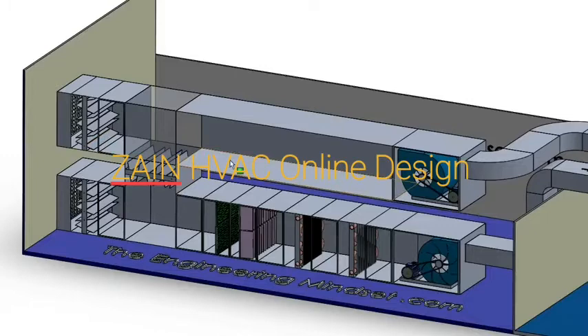Now, you don't have to have this here. You could have that duct straight across and this also duct straight across, so that these two are not connected. And that's certainly the way in the past it was achieved, but it's really expensive to do that. So if you imagine, if you didn't have this connection here, then all that air that you brought in would have to be filtered, heated, and then cooled. And then you've spent all that money in the heating and the cooling.